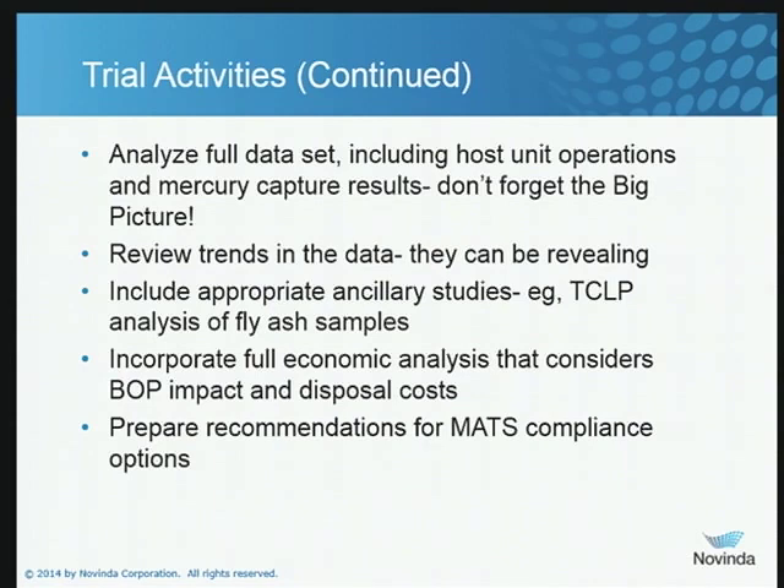Make certain you look at trends in the data, because that can be very revealing. This is one of the reasons that at Novinda we are very insistent that we have CEMS in the measurement suite. CEMS give you that ability to look at trends — you can't see that when you're running a one, two, or four-hour Method 30B trap. Look at other ancillary studies that may be required, such as TCLPs and analysis of fly ash or scrubber samples. Incorporate a full economic analysis including capital costs, operating costs, balance of plant impact, and in some cases disposal costs. Then finish it up with a recommendation for MATS compliance so that your management can have a technically valid and substantiated decision to make.